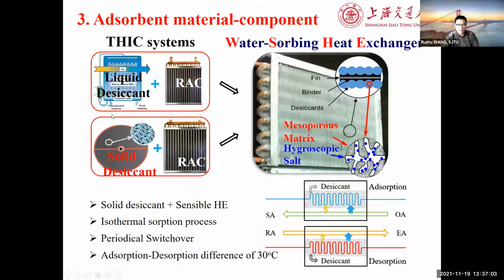And what's important is that we try to use this for a temperature and humidity independent control system, because for air conditioning, you have liquid desiccant with sensible heat exchangers for dehumidification and cooling, or using a desiccant rotor for dehumidification and a sensible heat exchanger for cooling. In this case, compared to a normal evaporation air conditioning system, you could get an evaporation temperature of more than 15 degrees centigrade, because dehumidification is done by the liquid or solid desiccant. But now we have this kind of desiccant coated on the heat exchanger. So this will be a water absorbing heat exchanger.